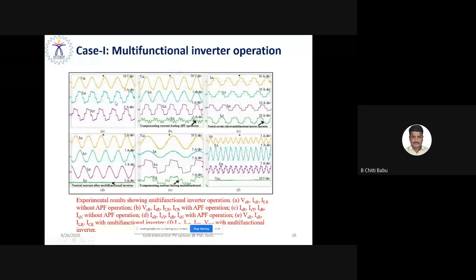So the effect opposes the cause. You can see the grid current is distorted; it is not sinusoidal. So this is without the multifunctional inverter. Now, as you connect a multifunctional inverter as a shunt active power filter at the PCC, it injects a compensating current, and you can see your supply current becomes sinusoidal. This is with the active power filter.